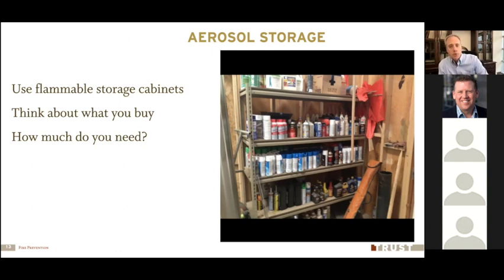And so we should follow the same rule of thumb on these flammable aerosols as we do with other flammable fuels like gasoline. A good general rule, depending on the occupancy of your building, is if you've got more than 5 gallons worth of this flammable fuel, however it's stored, aerosol or otherwise, let's make sure we have that in a flammables room or in a flammable storage cabinet. Think about what you're buying.